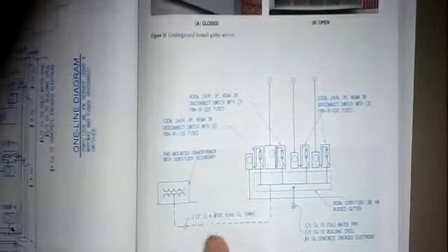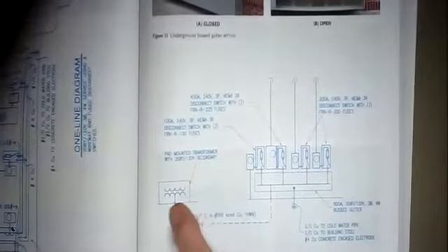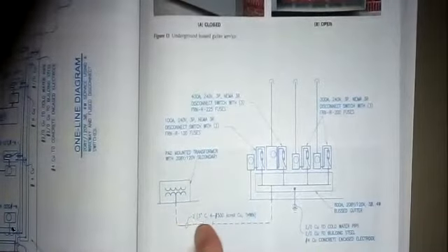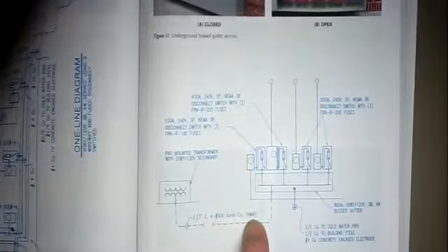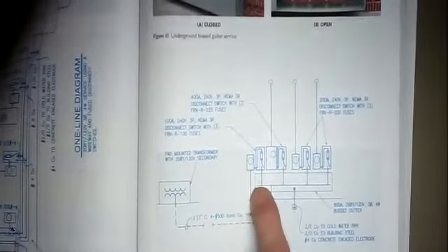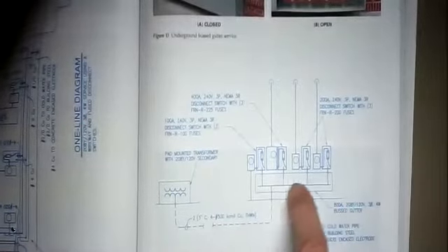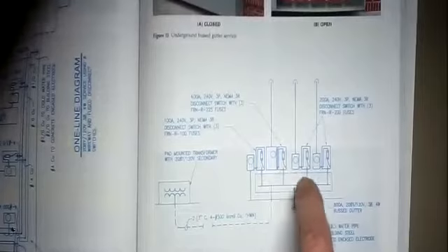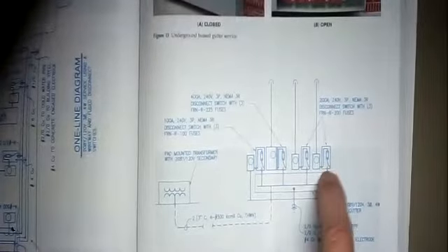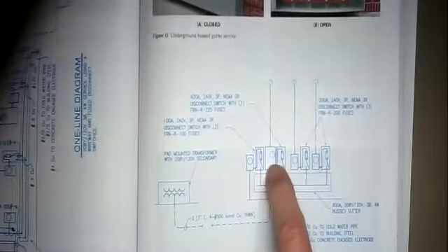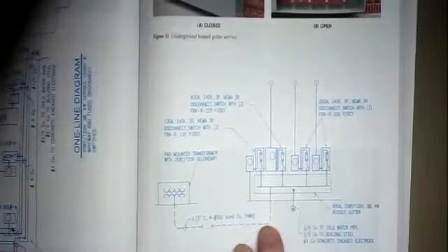Okay, here's another example of an incoming service. And again, here's the transformer out on a pad. This is a one-line diagram saying they have 2 3-inch conduits with 4 500 kcmil copper THW conductors coming up into this busway. And there's the busway, and it comes up to each of these disconnects. They're cold sequencing. They're putting the disconnects before the meter so that they can turn off the main disconnect and then they can service the meter safely. So that's cold sequencing. That's a good drawing of cold sequencing.